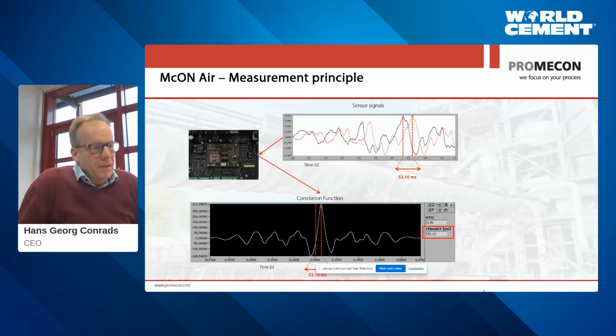And the distance is fixed by the sensors, and the sensors reach into the duct perpendicularly to the axis of the duct. And that is a big advantage as well, because we're measuring a vector. Our velocity is not a scalar value, but it's a vector, and the direction of that vector is pointing parallel to the duct. So if you have swirl in the duct or any other lateral component of flow, this will not be detected by our sensors. Our sensors will only measure the velocity in direction of a duct. And that is a very big advantage because it gives you the true throughput through a duct.